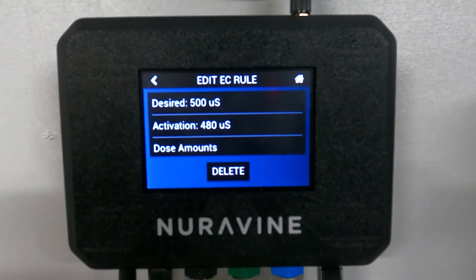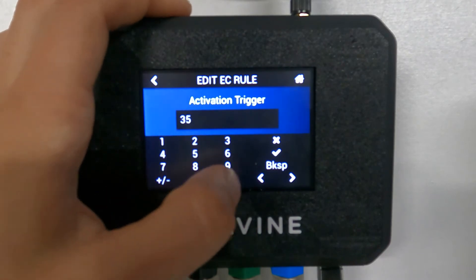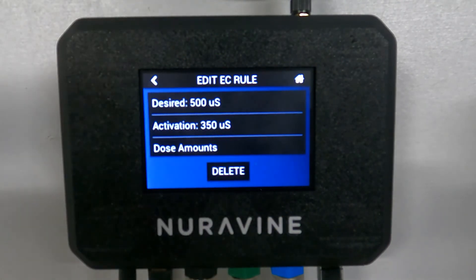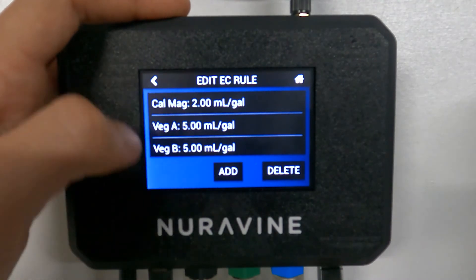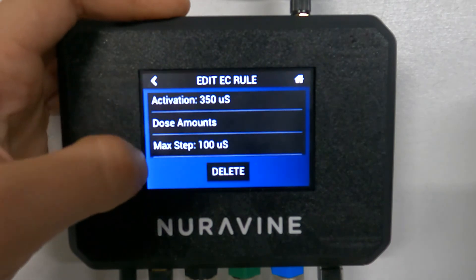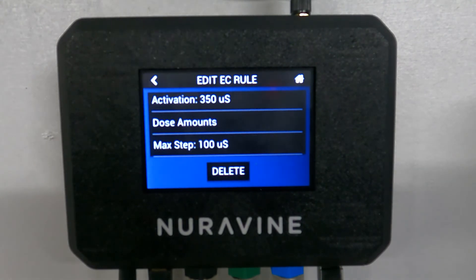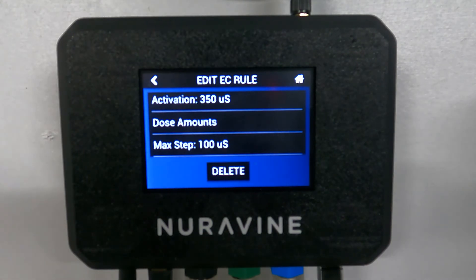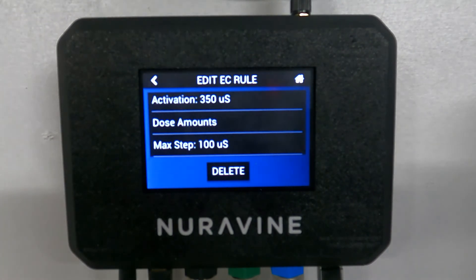Once it goes 480 or below, it's going to dose until it gets back up to 500. You might want to lower that activation threshold — say down to 350 — so it waits until it goes all the way down to 350 before bringing it back up to 500, increasing that range. Dose amounts show what we've entered and you can change them. The max step is 100 microsiemens, which means it's not going to try to dose it all in one big dose — it jumps up in steps of 100, and as it gets closer to 500, it'll slow down even more.